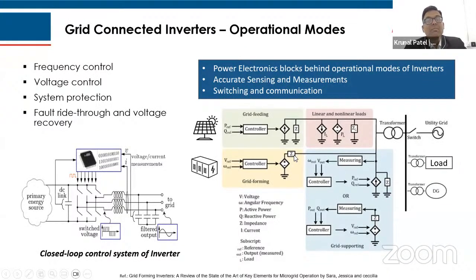Now, at the output of the voltage source there is an impedance, which plays a very important role in identifying the right impedance matching with the grid requirement, and for that this Z plays a virtual role. Currently, many technologies are available to match this impedance with the grid requirement, and virtual impedance matching is the latest, where the impedance is adapted by the controller and adjusted automatically with respect to the proper grid voltage and frequency. Apart from that, measurement units continuously sense the output of the AC side of the connection and provide closed-loop feedback to the internal microcontroller of any grid-connected inverter. Based on that, the overall microgrid scenario works.